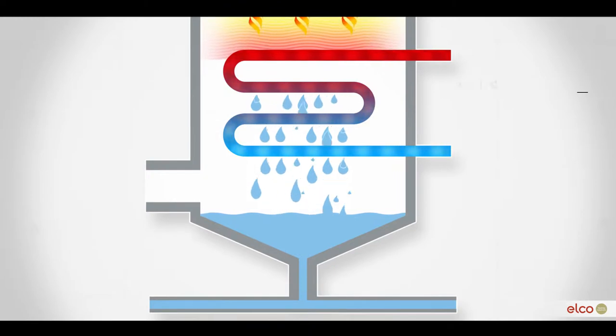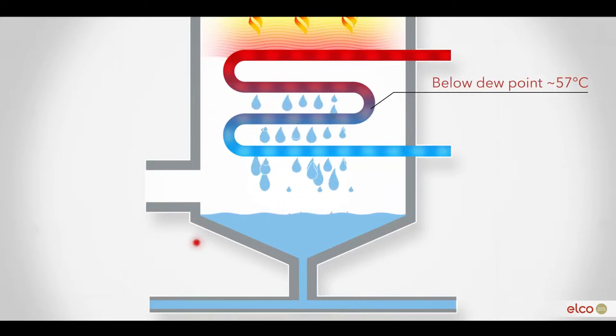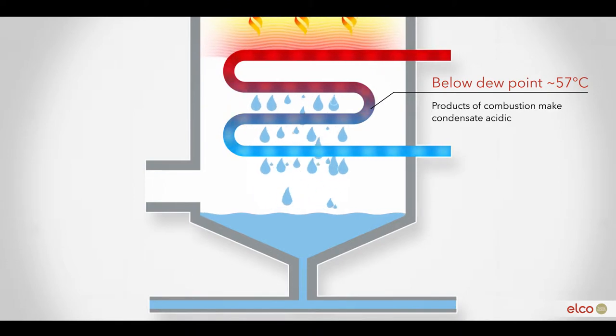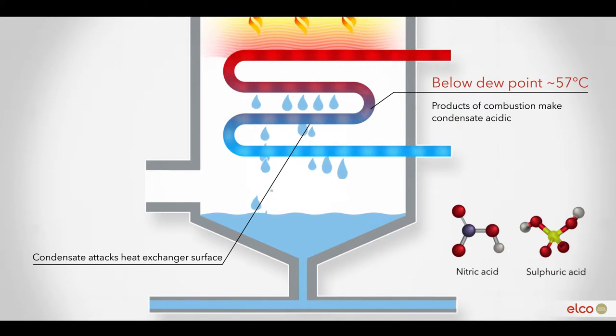But when the flue gases cool down further below the dew point of around 57 degrees Celsius and condensate forms, the products of combustion make the condensate acidic. This condensate attacks the heat exchanger's surface.